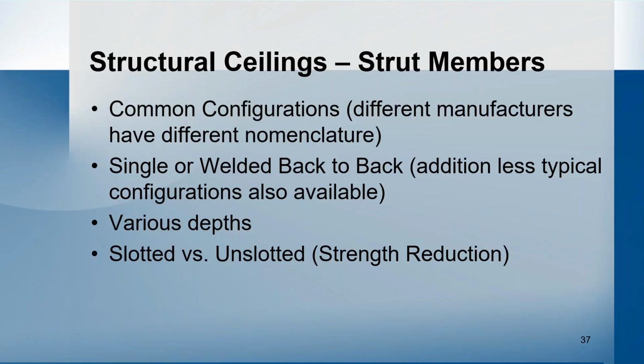So for the strut members themselves, there's some very common configurations. Different manufacturers have a lot of different nomenclature, and it's kind of all over the map, what the nomenclature means and how it's laid out. There's single or welded back-to-back. There's also some additional less typical configurations available, but those aren't typically used for the structural ceilings. Get used somewhat for the hot aisle containment that I'll mention a little bit. They come in various depths and either slotted versus unslotted. And when you're dealing with the slotted, you have a strength reduction in the slotted.